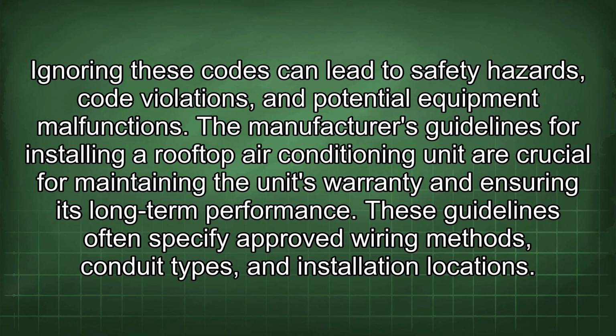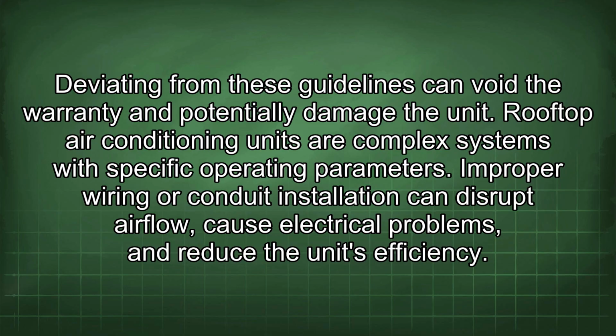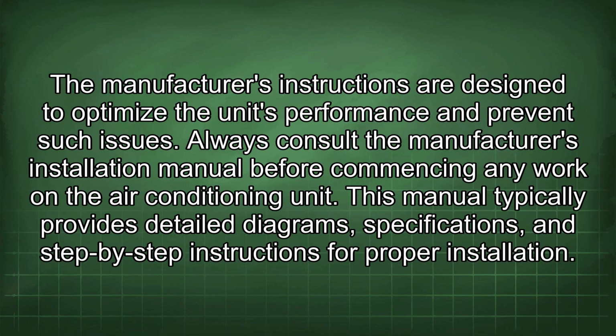The manufacturer's guidelines for installing a rooftop air conditioning unit are crucial for maintaining the unit's warranty and ensuring its long-term performance. These guidelines often specify approved wiring methods, conduit types, and installation locations. Deviating from these guidelines can void the warranty and potentially damage the unit. Rooftop air conditioning units are complex systems with specific operating parameters. Improper wiring or conduit installation can disrupt airflow, cause electrical problems, and reduce the unit's efficiency. The manufacturer's instructions are designed to optimize the unit's performance and prevent such issues.